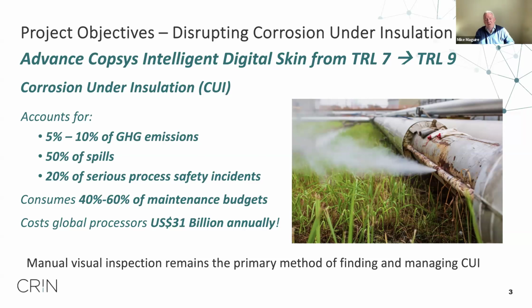It accounts for 5 to 10% of greenhouse gas emissions, which we'd like to eliminate, and 50% of spills. It's the root cause of about 20% of serious process safety incidents. If anyone remembers the Piper Alpha disaster some years ago, there was a big CUI component in the breakdown of events that led to that disaster. It now consumes about 40 to 60% of maintenance budgets on aging process facilities, costing global processors about US $31 billion annually.